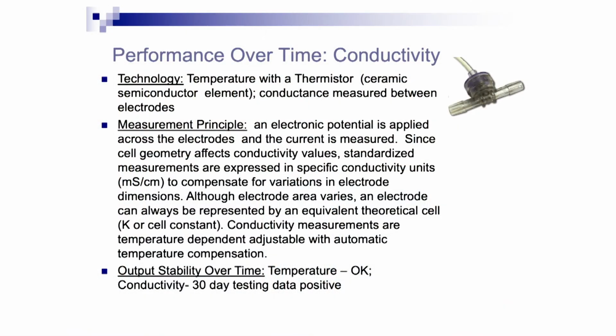Conductivity is measuring a current across the electrode electrical potential. There was a little less data available because a lot of people are calibrating conductivity sensors on a regular basis as they use them. Each conductivity cell, because they're slightly unique in geometry, has what's called a K factor. And so we looked at a certain K factor that gave it accuracy.